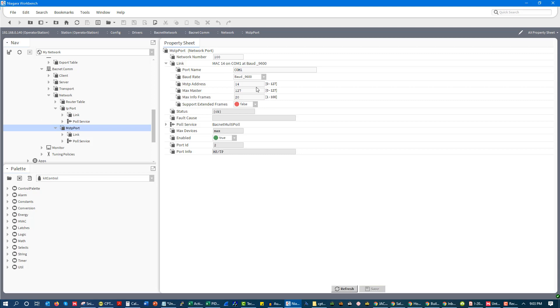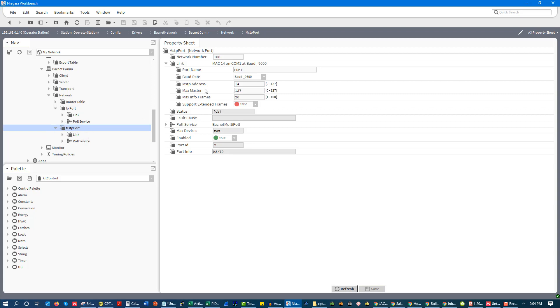And then on the MSTP side, we have some different settings. So IP is largely logical, meaning there's no physical IP address. It doesn't exist. Whereas there is a physical DIP switch typically to set your MSTP MAC address. IP is all logical, and the settings are logical, whereas MSTP, the settings are physical. Now, with it being a physical serial network trunk, we're going to see that we can adjust the speed via this baud rate. You want to have the baud rate the same for every controller that's on that network segment.